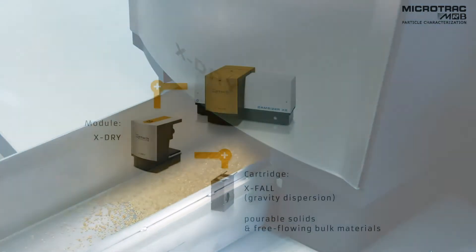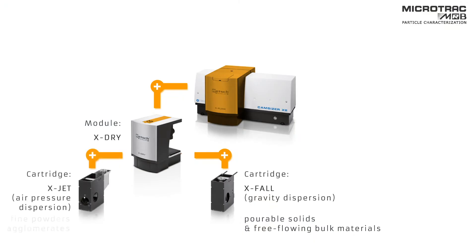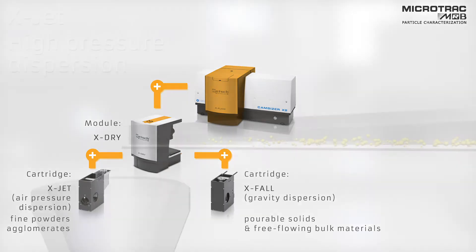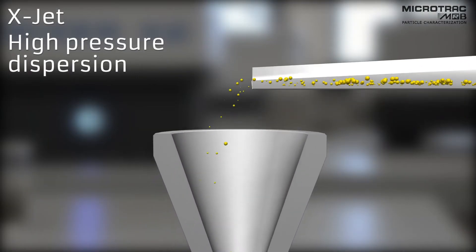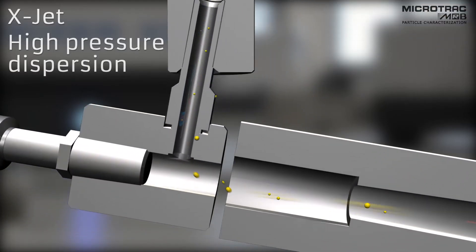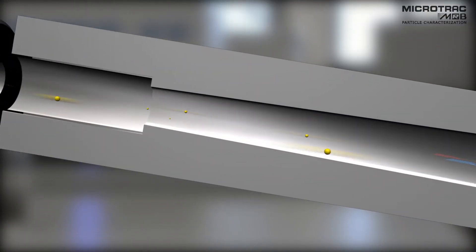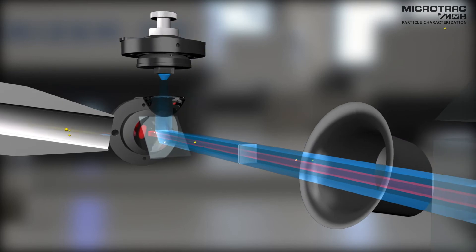The whole sample can be recovered after the measurement. The high-pressure cartridge X-jet is suitable for fine powders and agglomerated material. The sample is dispersed in an airflow which ensures that agglomerates, which would falsify the measurement results, are broken down prior to detection.